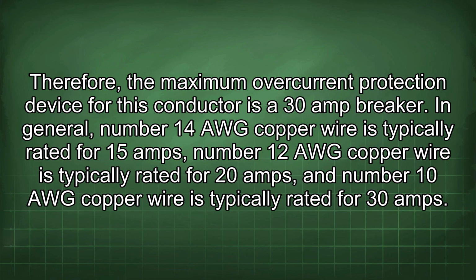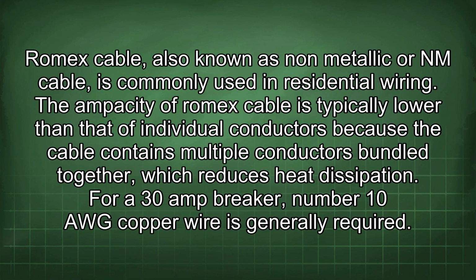Number 12 AWG copper wire is typically rated for 20 amps, and number 10 AWG copper wire is typically rated for 30 amps. Romex cable, also known as non-metallic or NM cable, is commonly used in residential wiring. The ampacity of Romex cable is typically lower than that of individual conductors because the cable contains multiple conductors bundled together, which reduces heat dissipation.